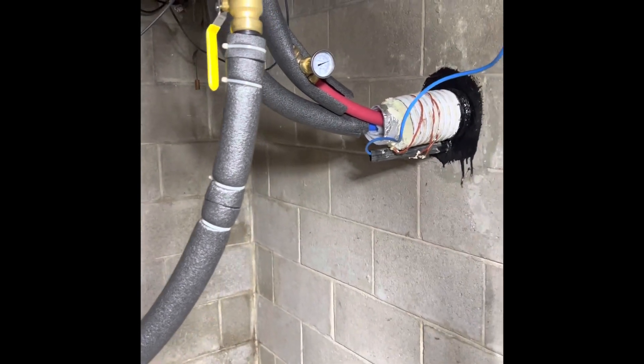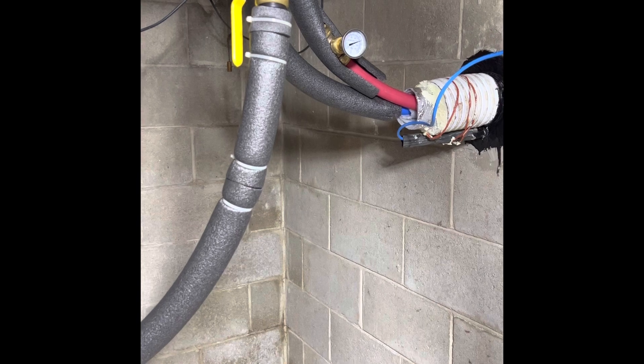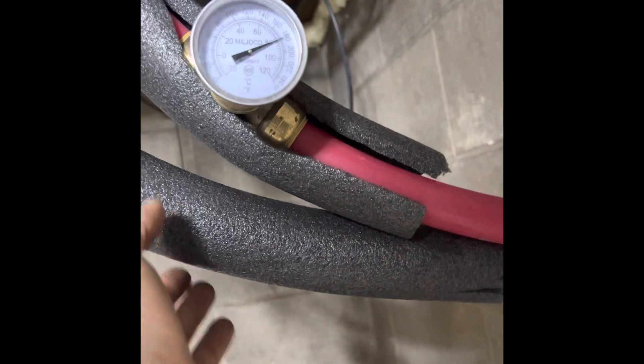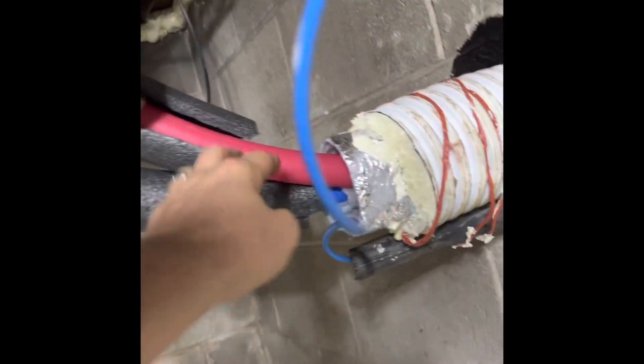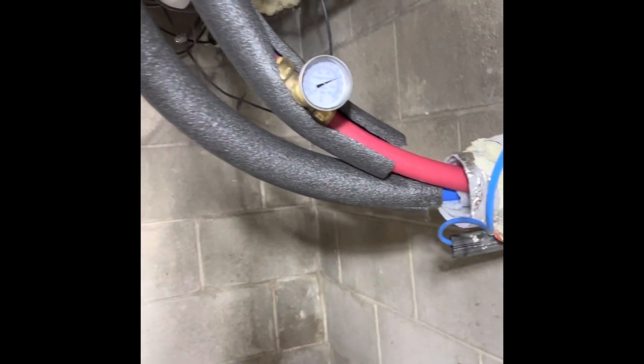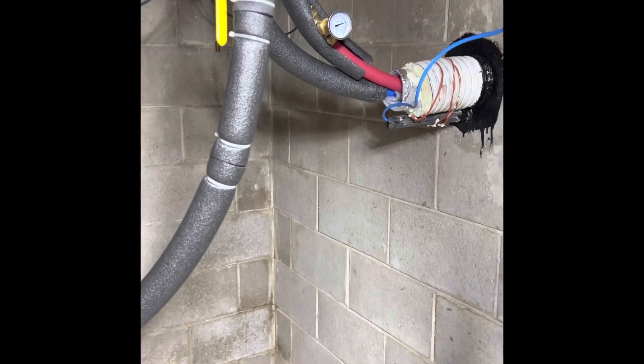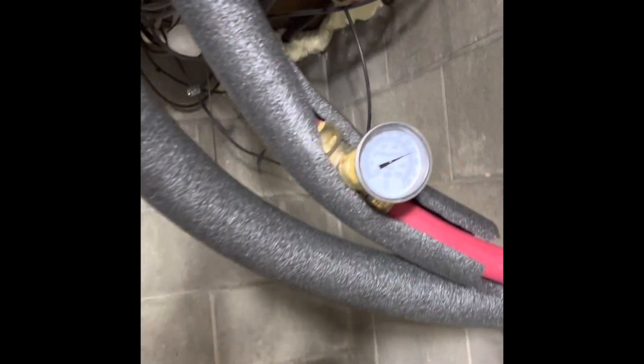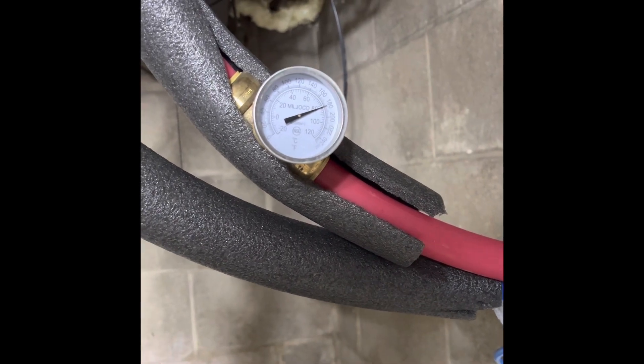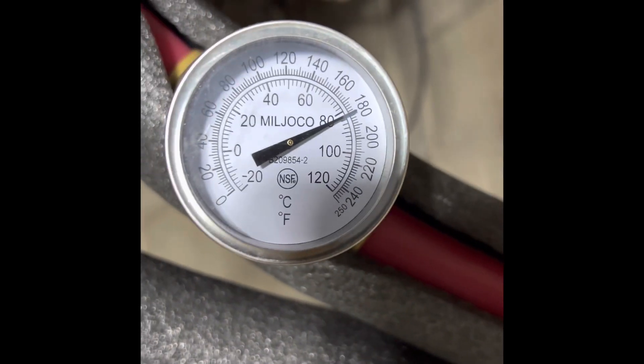To me I would consider that to be a success. I know going out it's probably losing maybe 20 degrees when stuff is running. I'll eventually put another temp gauge here. I know some guys say they only get so much temperature out of their boiler when it's at 180 degrees, but this proves right here that you should be reading what the boiler says.